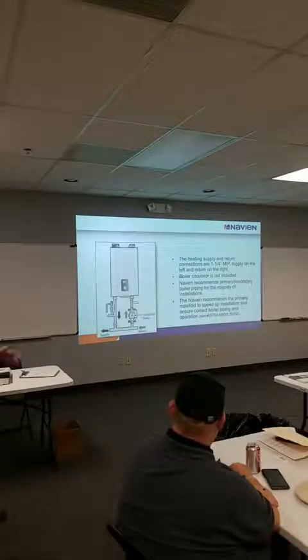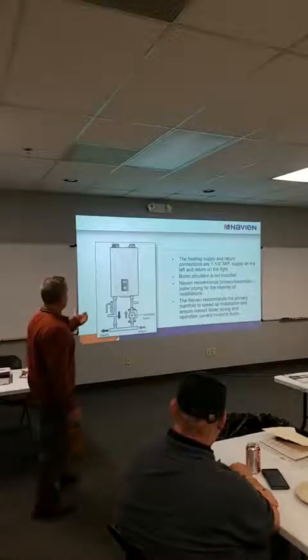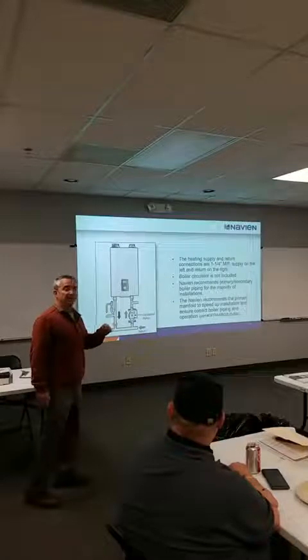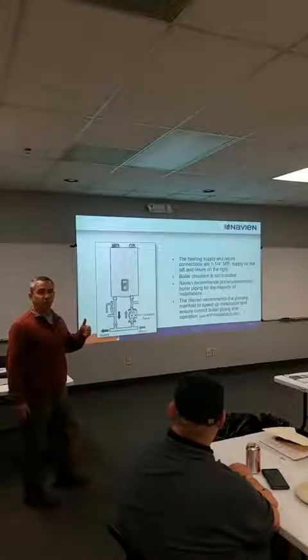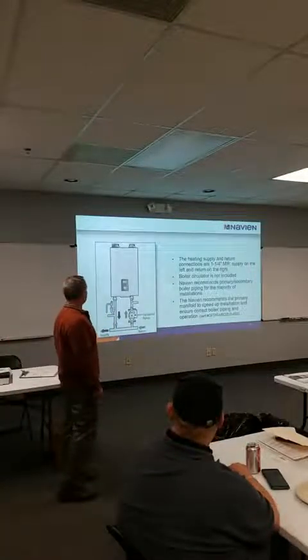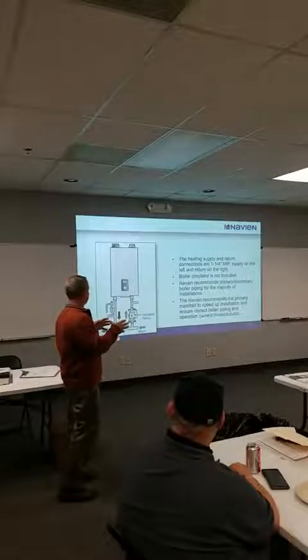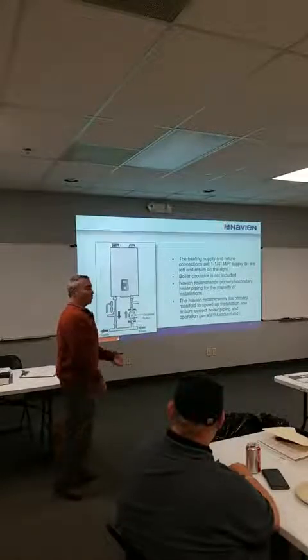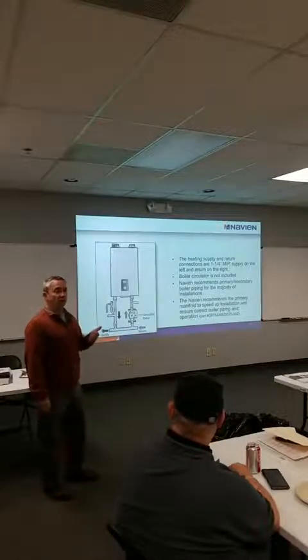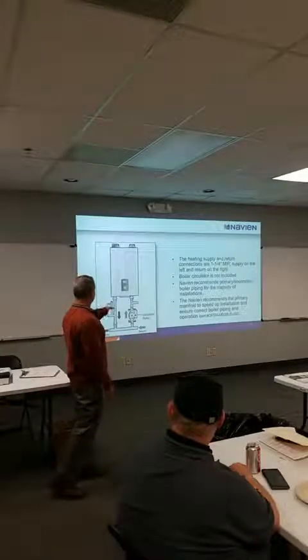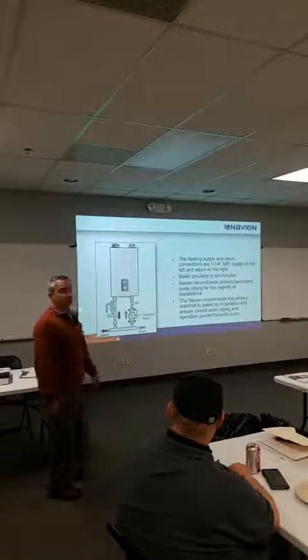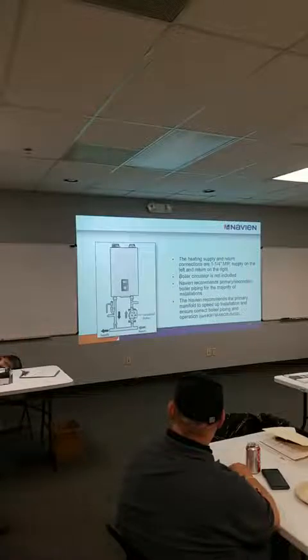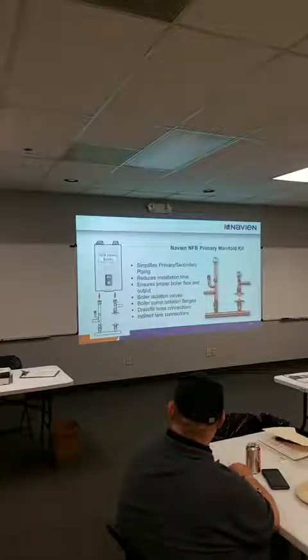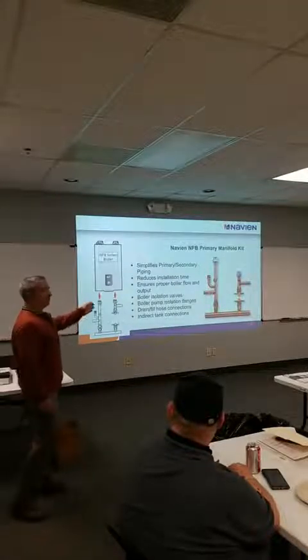So, the manifold is a little different on our NFB than it is on the NHB. It's reversed because of the flow, because we had to change it up a little because of the size of that fire tube heat exchanger. Navien always pulls water back into the boilers, so it looks like the same kind of manifold, just the pump's on the other side. And again, your pump dimensions are in the manifold, or in the manual itself. This is flanged. You know, these aren't inexpensive, but they give you everything you need.